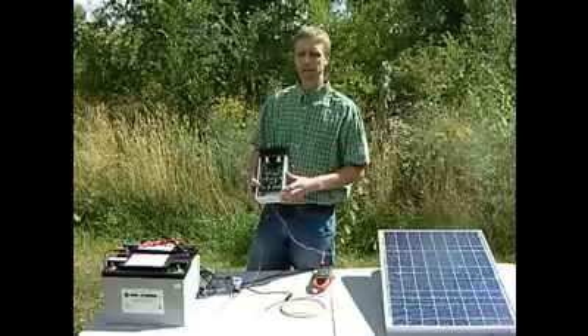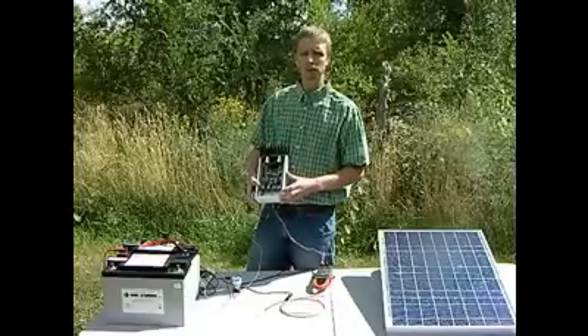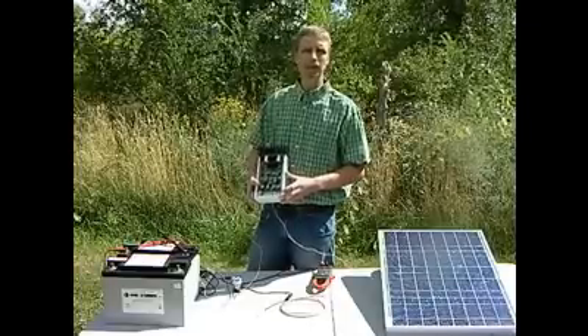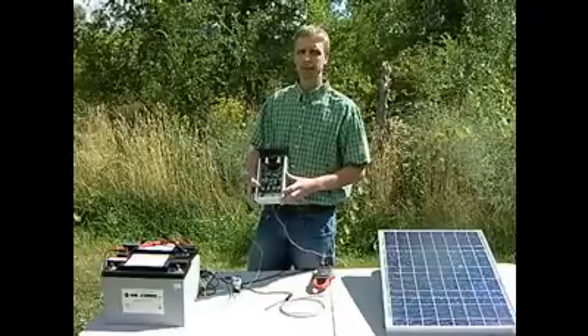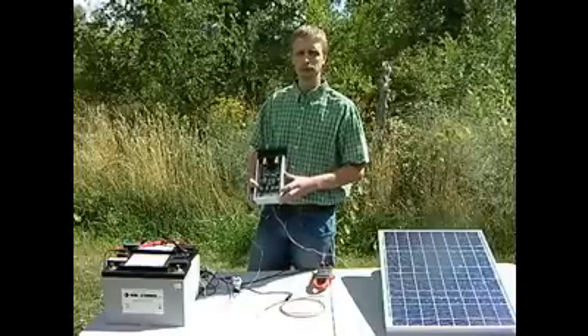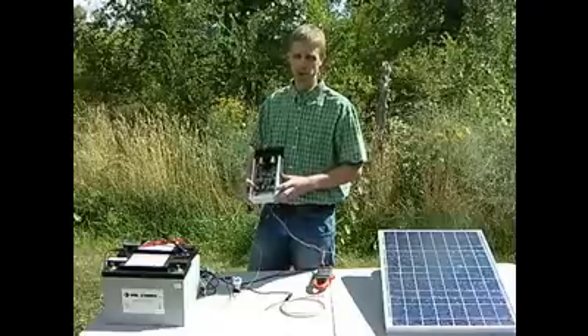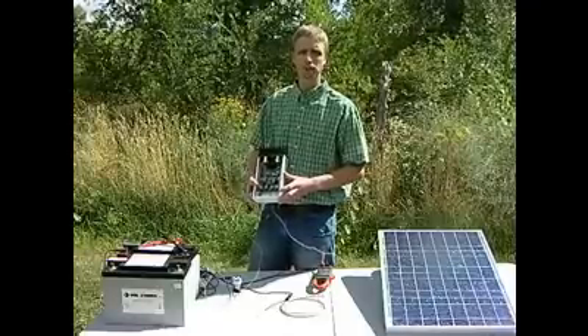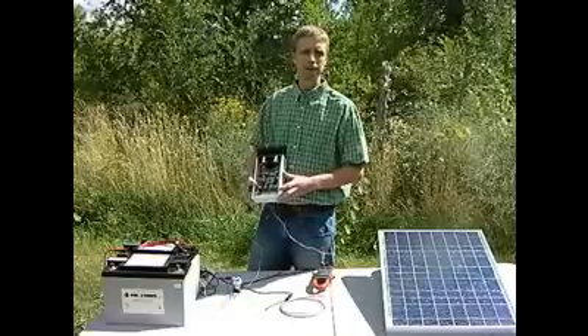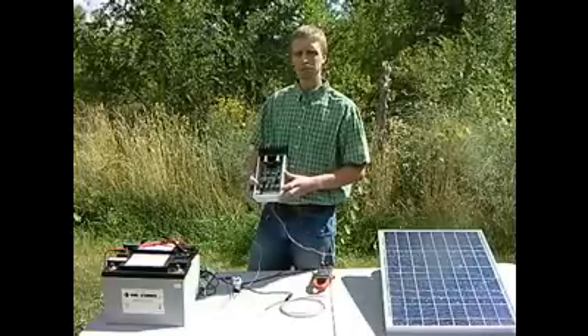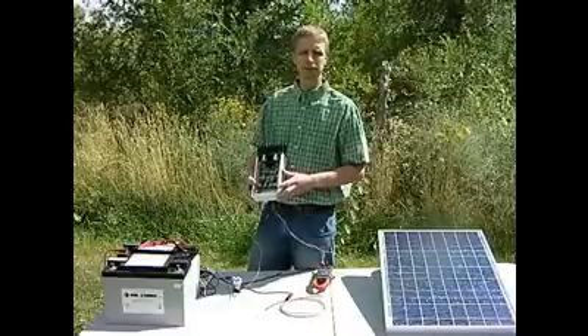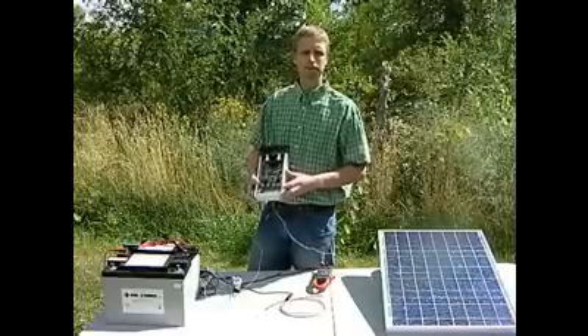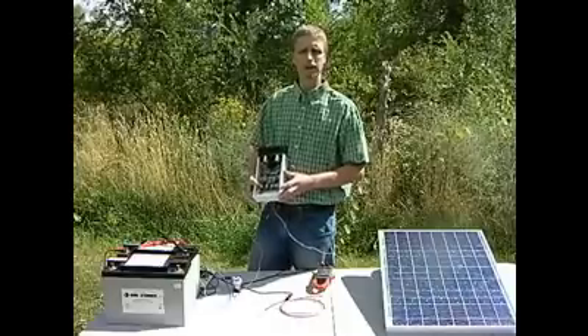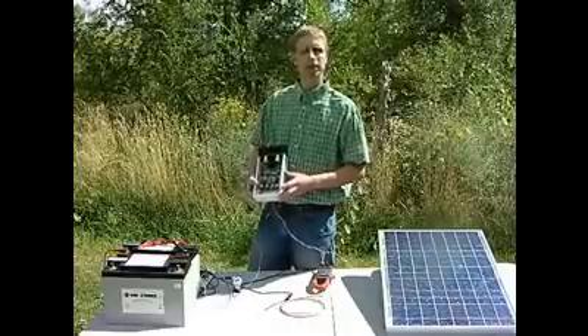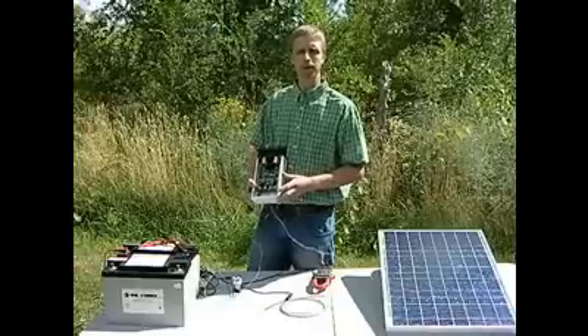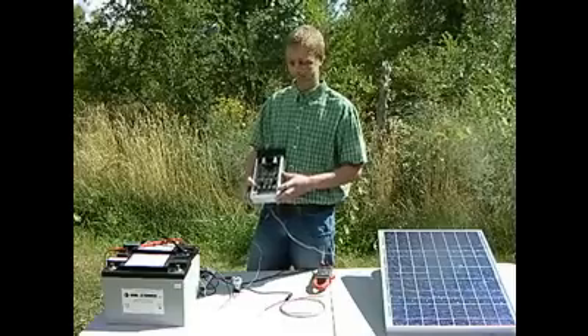The thing you need to be careful of is that on a flooded battery, when you overcharge it or equalize charge it, you're going to be making hydrogen gas. So you need to be really careful that you don't have any sources of sparks. Make sure there's no way you can have a short circuit, because that hydrogen gas is explosive. As long as you're venting it, maybe with a breeze or a fan nearby, it can be safe to equalize charge a battery. A lot of modern battery chargers also have a feature that allows you to overcharge or equalize charge your battery. Just make sure you're careful while doing it that you don't ignite the hydrogen gas, because it can be explosive.